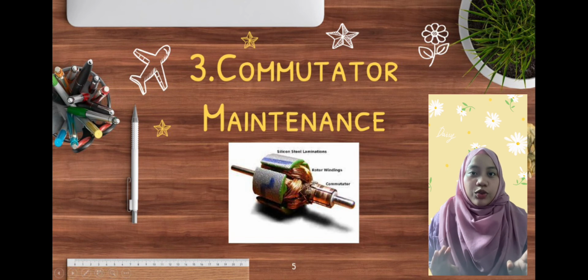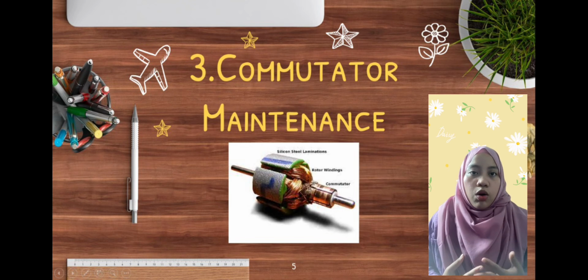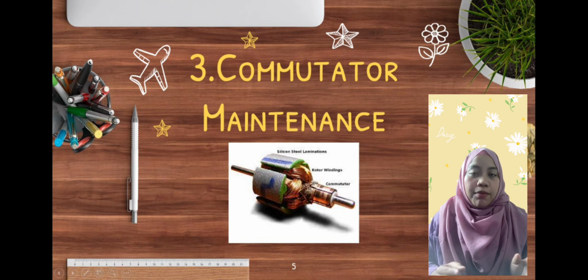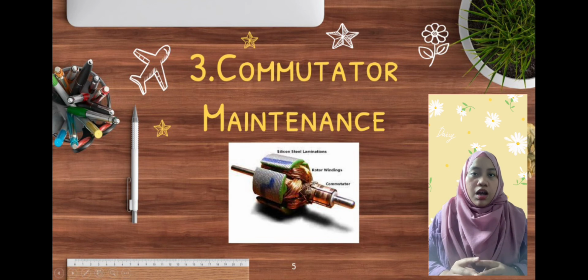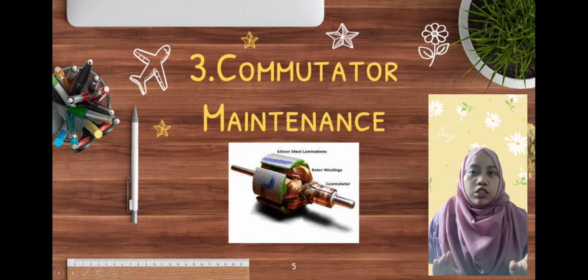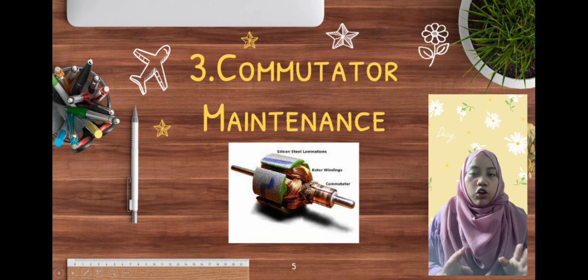It is very important to keep proper maintenance schedules to ensure the commutator stays round without run out on the surface. If the eccentricity of the commutator is not acceptable, you could end up with broken brushes and or brush springs. A commutator that is out of round can also lead to potential high bars, which can damage the brushes and cause excessive arcing where the brush contacts the copper bars. A well-balanced armature is also recommended to prevent the brushes from causing any unnecessary damage to the commutator.